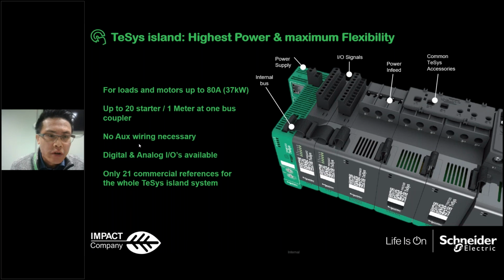There is no auxiliary wiring necessary because all the status of the contactors and the status of the motors is already gathered by the bus coupler. You can just have the data for the status of the contactors with these communications. So no need for auxiliary wiring, no auxiliary contact block, and you can have all the status of the motors.